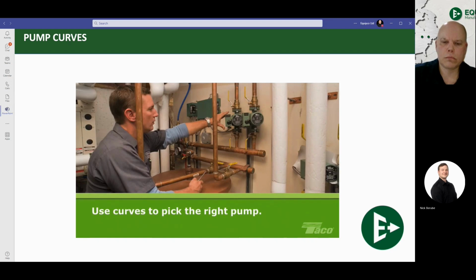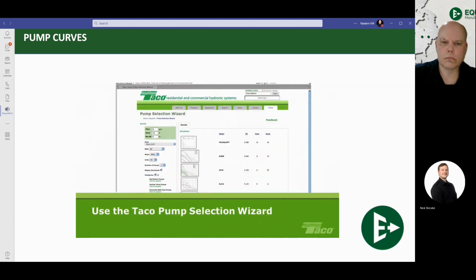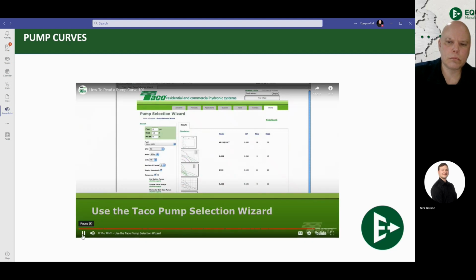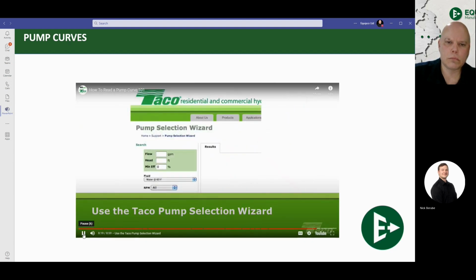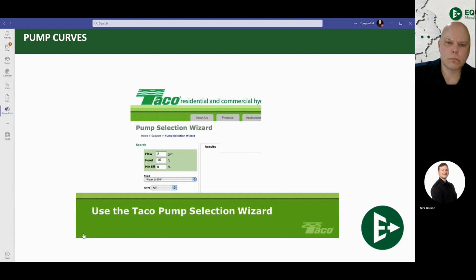Now you have the basic information that you need to read pump curves and use them to choose the right pump for any residential job. But there is still more information on the Taco website, plus a handy tool for finding pump curves. It's called the Pump Selection Wizard. Just put in the head and flow rate of your job, and the Pump Wizard will show you all the Taco pumps that meet those requirements.